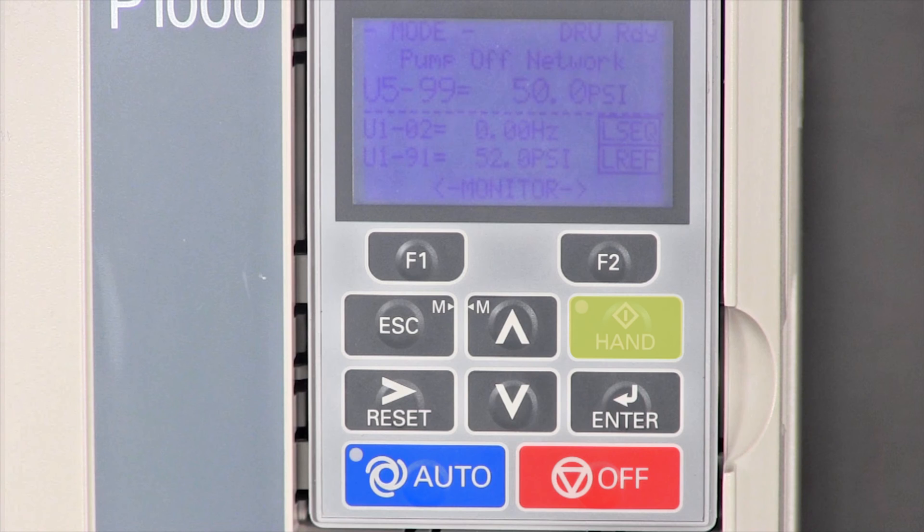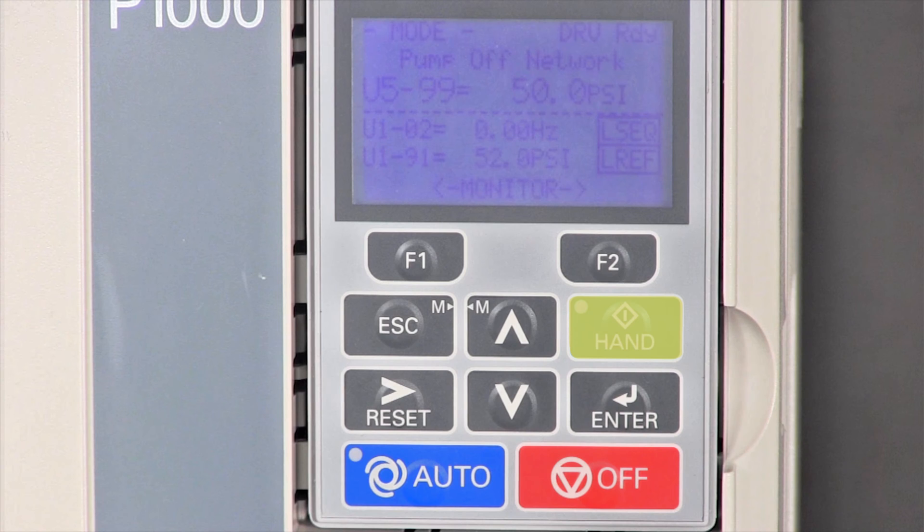Okay, the hand button. This will run the pump continually at a constant speed. This is used for troubleshooting and startup only. Never leave the pump running in hand mode. The off button is simply that. It turns off the pump.